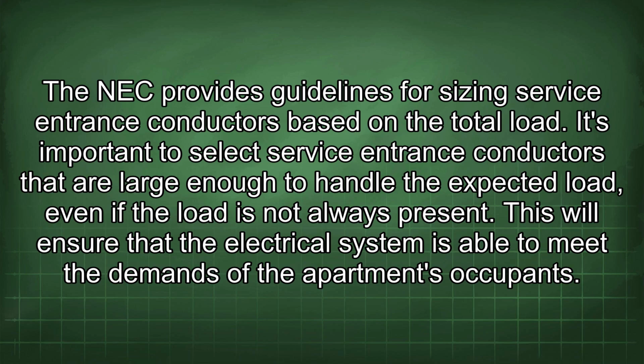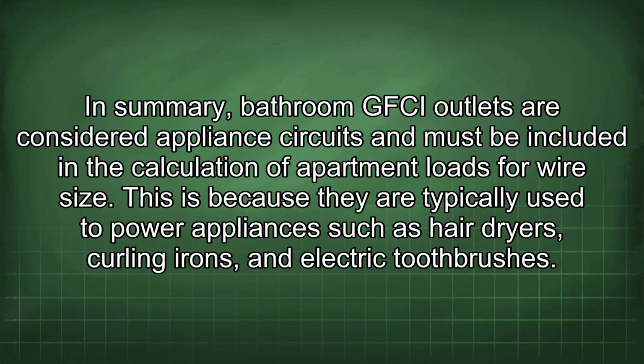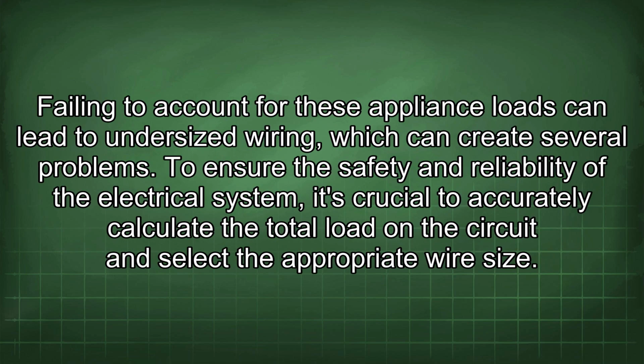This will ensure that the electrical system is able to meet the demands of the apartment's occupants. In summary, bathroom GFCI outlets are considered appliance circuits and must be included in the calculation of apartment loads for wire size. This is because they are typically used to power appliances such as hair dryers, curling irons, and electric toothbrushes. Failing to account for these appliance loads can lead to undersized wiring, which can create several problems.